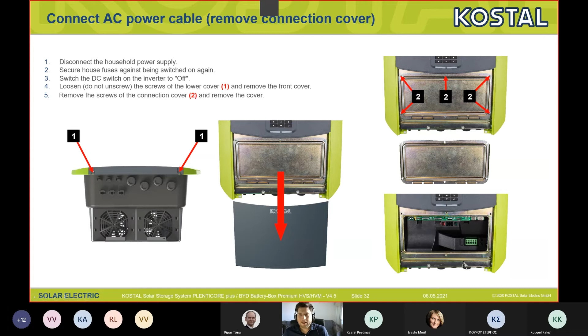You only have to disconnect the household power supply if you want to open the cover, then open the screws, and then you can also open the metal cover, loosen the screws of the lower cover, and then you will see the green terminal here, which is for the connection of the AC cable. You can use any type of cable, both solid types like NYM-J or NYY-J, and flexible cables can also be used. This is the AC terminal. The maximum cross section is 6 square millimeters.